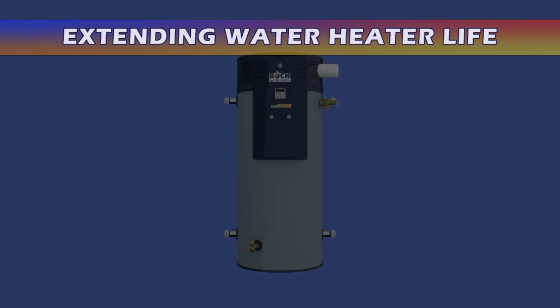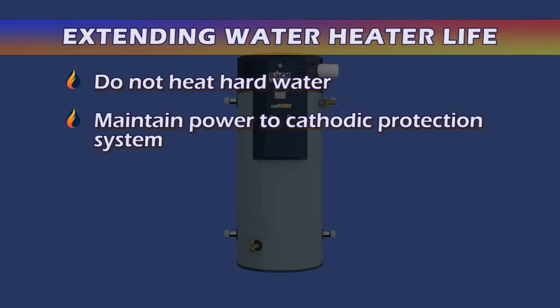The following guidelines can help extend the life of the water heater. First, do not try to heat hard water, as this will drastically reduce heater life. Install a water softener or another scale-reducing water treatment system if hard water conditions exist. Second, be sure power is maintained to the cathodic protection system at all times. If power is to be removed for an extended period, the water heater must be drained.